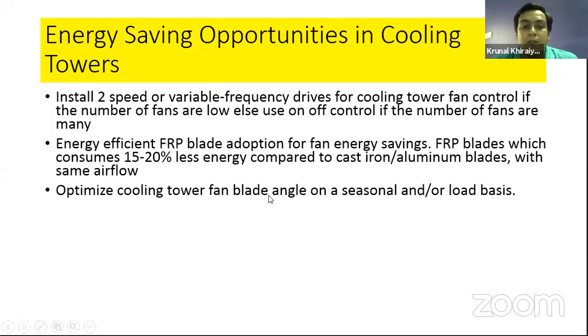Then optimize the cooling. Yes, based on the load and the seasonal variations, you need to change the blade angle. The blade angle is changed using the characteristic curves available for the fan.